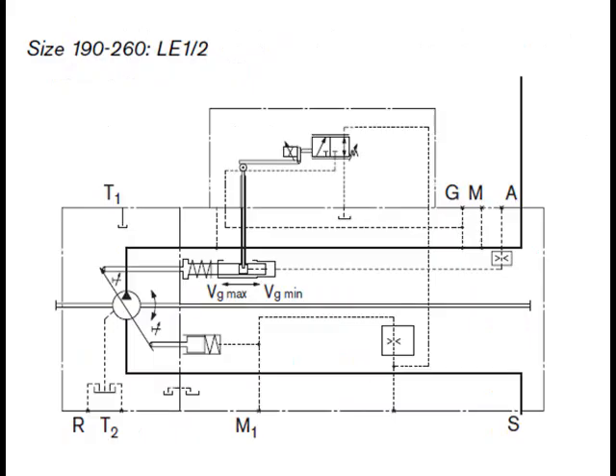LRH2-6 hydraulic stroke limiter — positive characteristic. Control from VG min to VG max: with increasing pilot pressure the pump swivels to a higher displacement. Start of control at VG min can be set from 4 to 10 bar. State start of control in clear text in the order. Starting position without control signal or pilot pressure: at operating pressure and external control pressure 30 bar, VG min. Characteristic H2: increase in pilot pressure, VG min to VG max, delta P equals 25 bar.